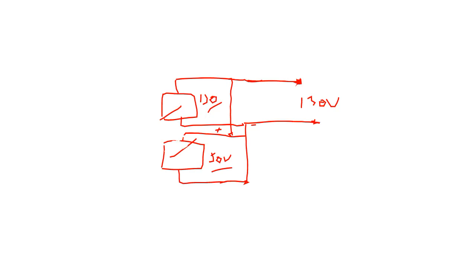Let me make it bigger. If we remove this charger here, and we make that a battery, and we make this a battery, okay, and let's make that 135 volts because that's what it should be for a 60-cell lead acid battery. In truth, if you disconnected, let's put a disconnect in there. If you disconnected this battery relatively quickly, that battery will go down to around about 127 volts. That is what's called the open cell voltage of the battery. And it will sit there for a very long period of time. And then as soon as you close that disconnect, it will go straight back up to 135 volts because it's in parallel with this charger here.